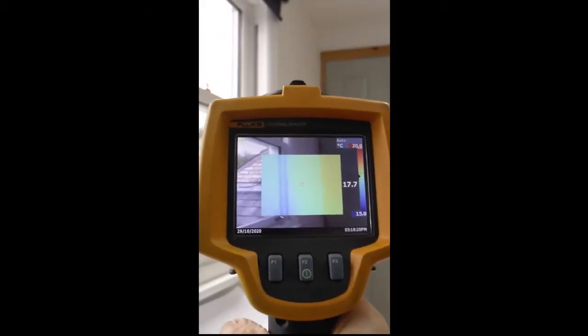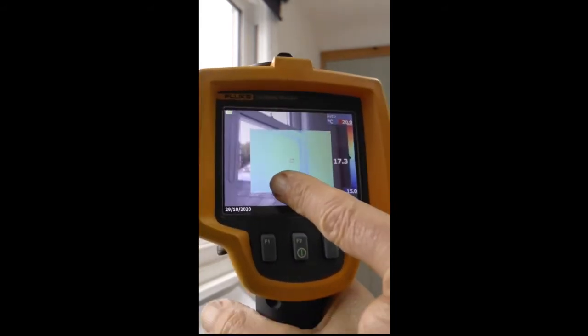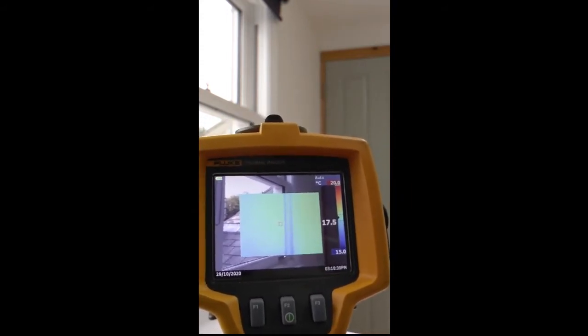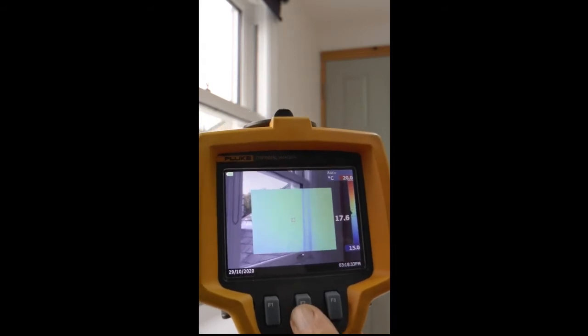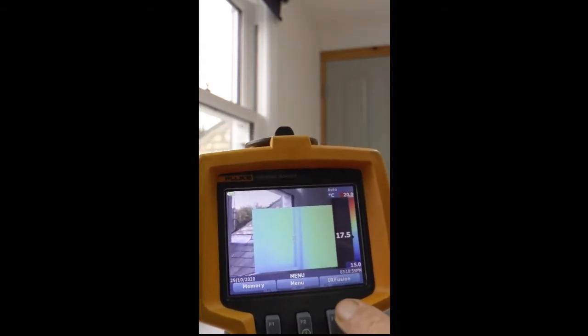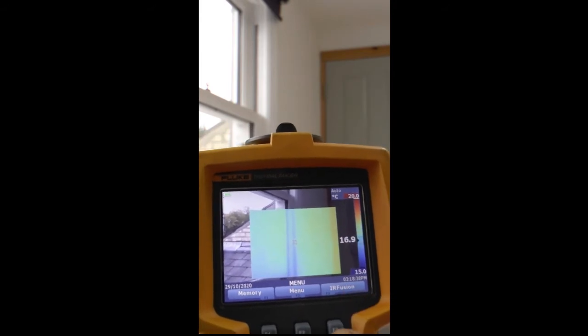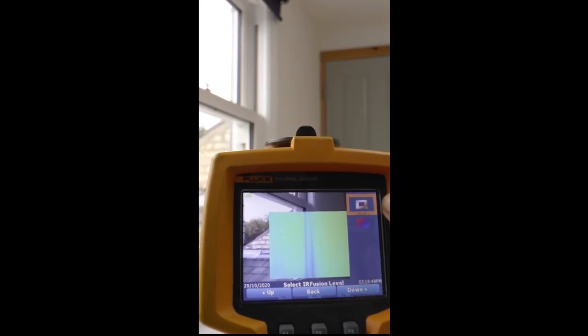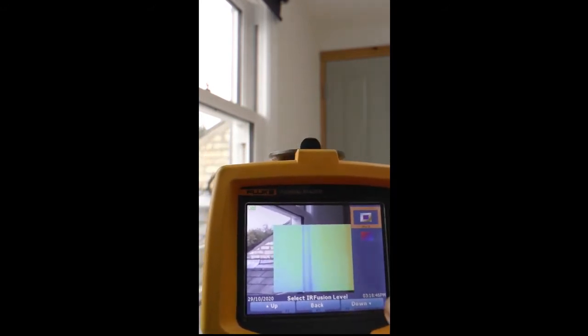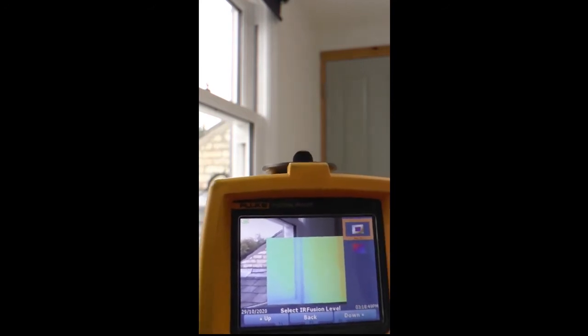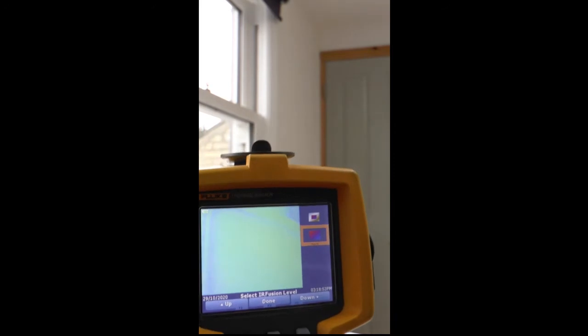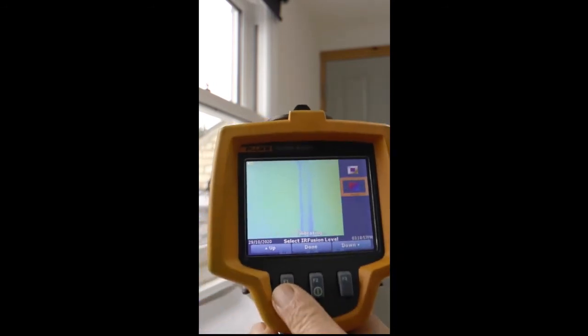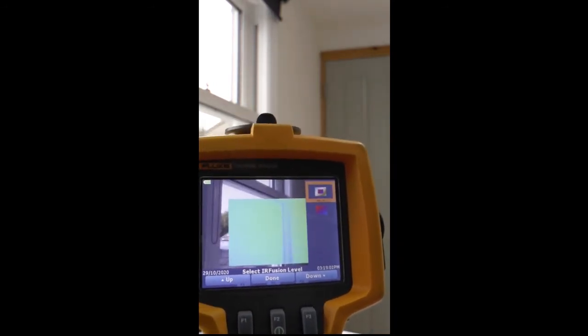Finally, let's check that the display is showing a thermal image in the middle and a visible image around the outside, which is what we want. If it's not showing that, then go through the menus and press F2. We want this option here: IR Fusion. Select that. At the moment we've got this picture-in-picture selection. If I go down here, it becomes all infrared, which is harder to interpret. So I recommend going back up here—we want this option with picture-in-picture.